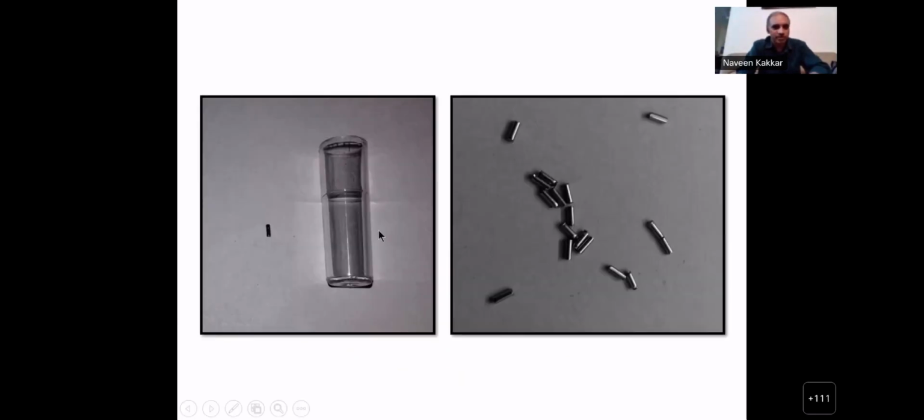The problem we found out later, about 3 days later. When we use the cuvette for a semi-automated analyzer, they give you these magnetic stirrers, which rotate and mix the reagent while the testing is being done. What we found out was that the company supplying these had the cuvettes, but they ran out of the packet of stirrers. What they did was, from the local Ludhiana market, they got somebody to have these wires cut and made stirrers, makeshift stirrers, thinking they won't matter. But the iron content for the magnet was poor.